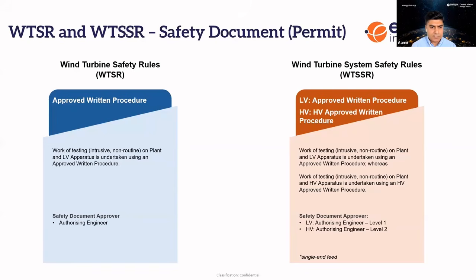To be specific on the sanction for test, the rules require that whenever a sanction for test element is part of the HV approved written procedure, that work or testing part shall be completed before any transfer or surrender of the document. This ensures that the safety precautions removed, such as the circumventing earth during the sanction for test, create a scenario which needs to be very carefully managed. Therefore it's a requirement that the full testing element needs to be completed before any surrendering is required.